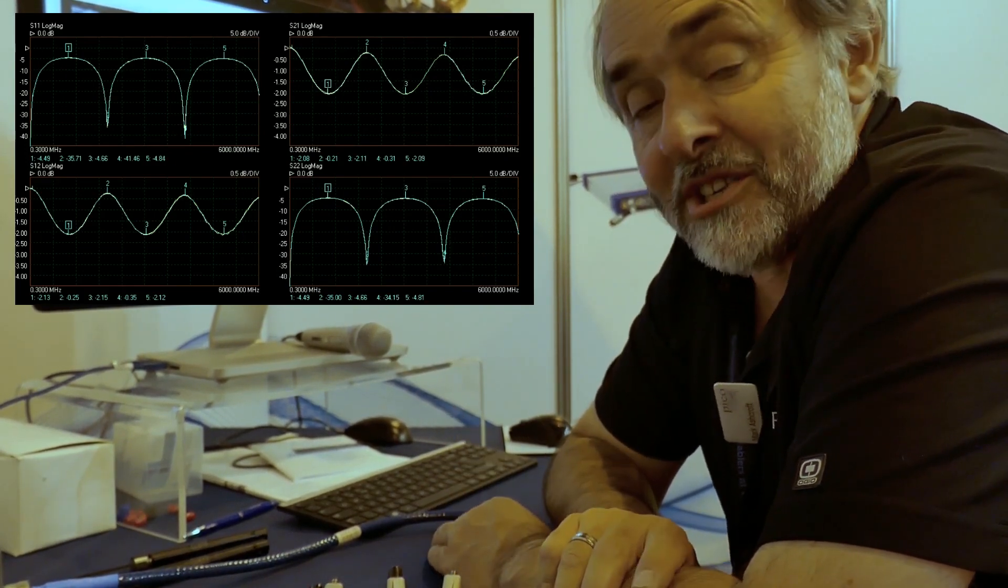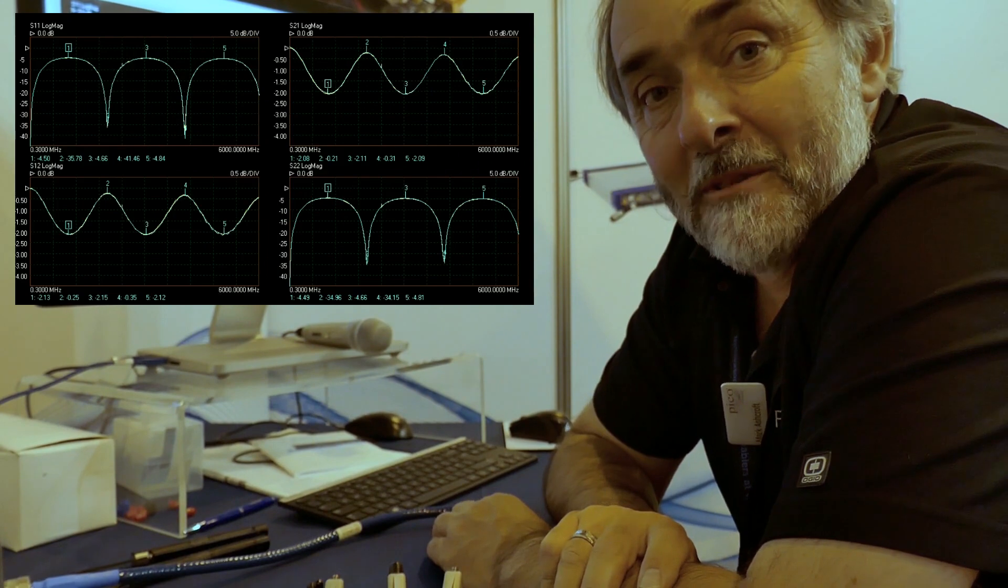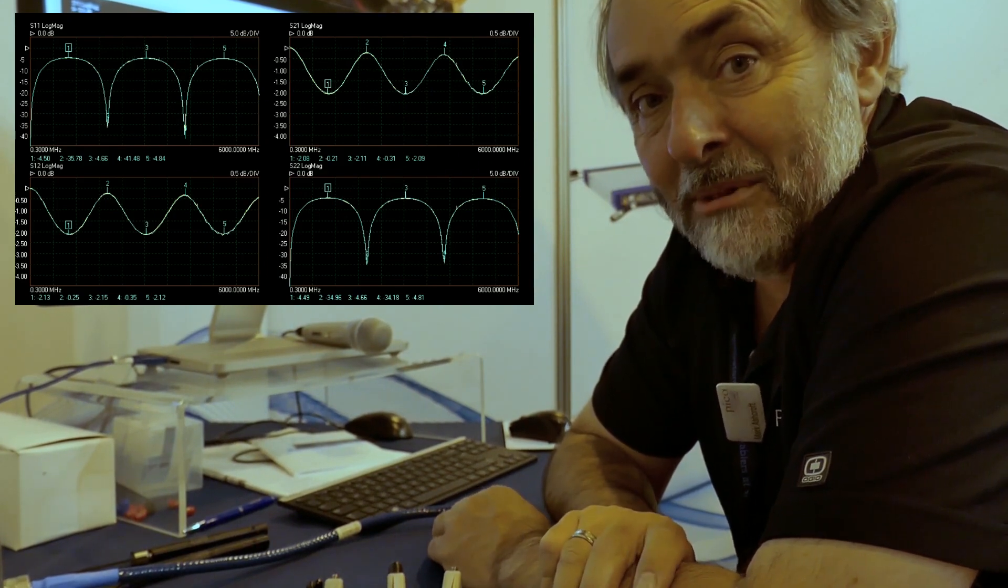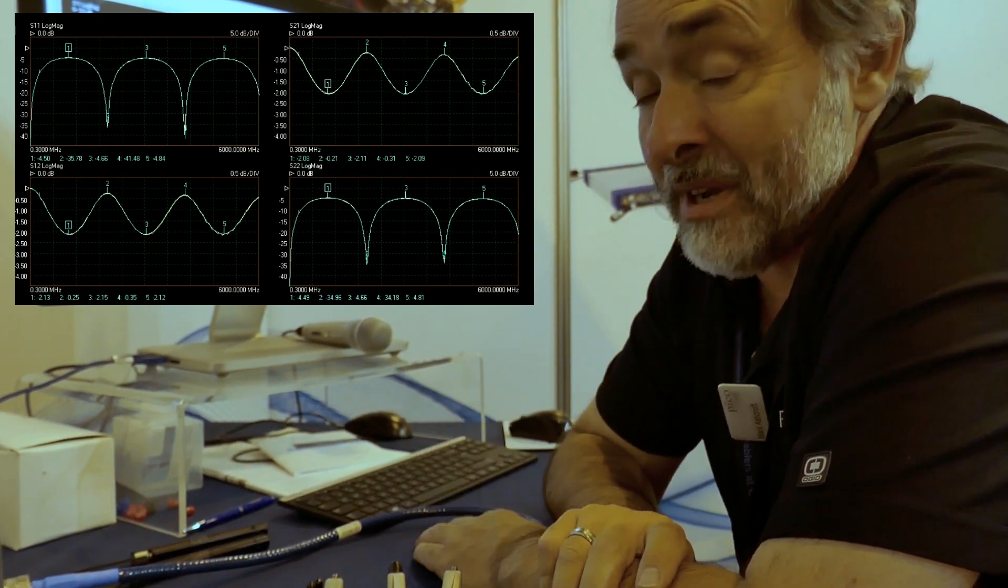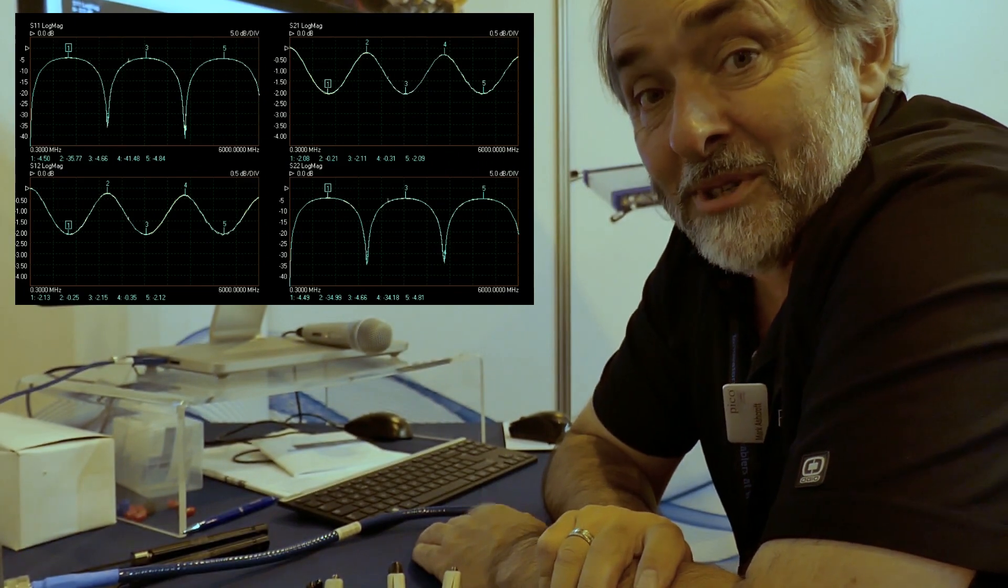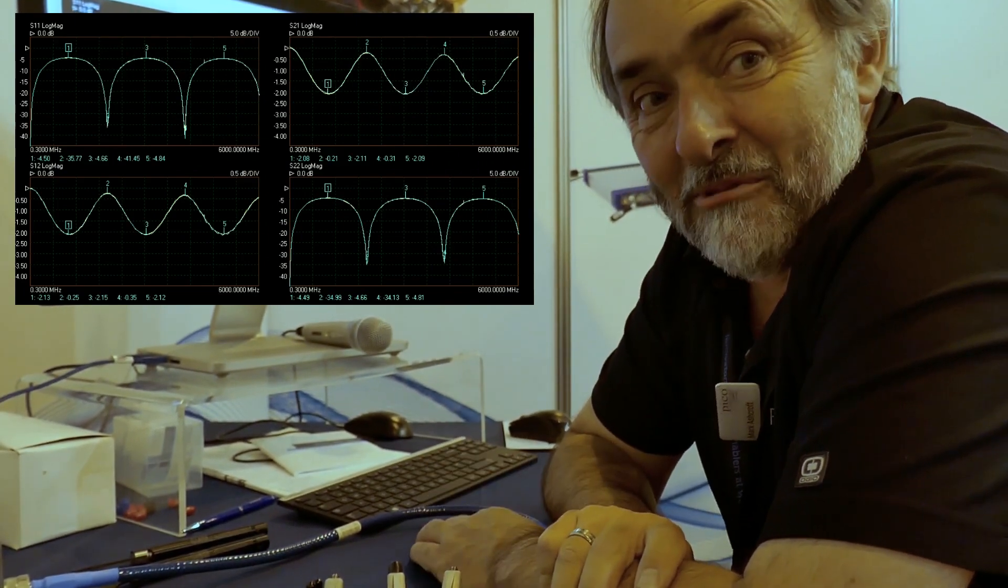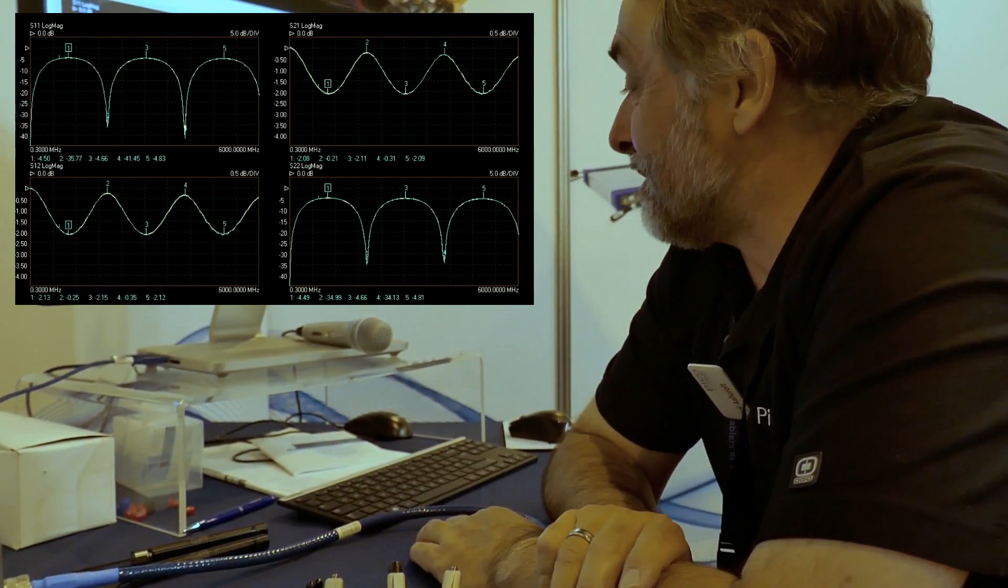Had we not had a check standard, we may never have found that we'd mixed up the calibration standards. There are of course many other things that can go wrong in a measurement, but stumbling across that one kept us thinking for quite some time.